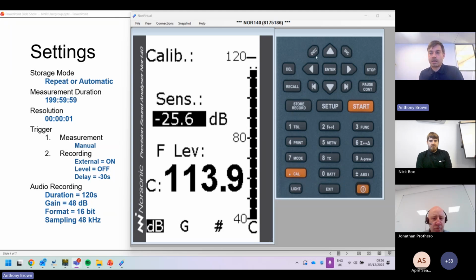So when I press this dec key, it will get me to 114 eventually, because it just changes this value here. On your meters, this will be different to mine, but it'll be around -25, -26. As long as it's somewhere around that figure, then it's fine. If it starts changing to something like -29 or -21, then you might have an issue with the microphone. So you might just need to send it in for calibration or something, and we can check it out.